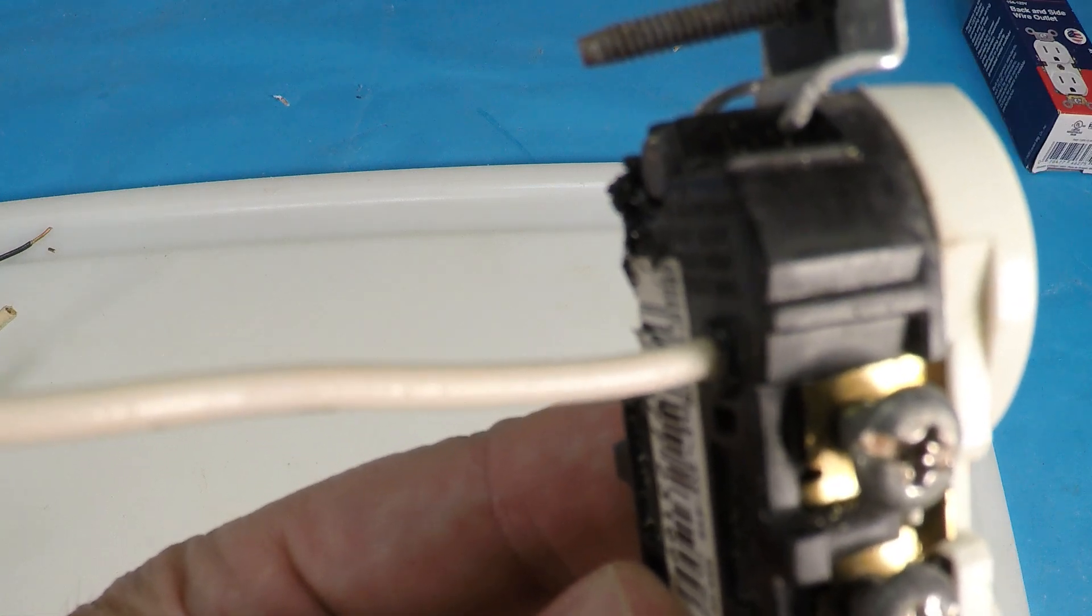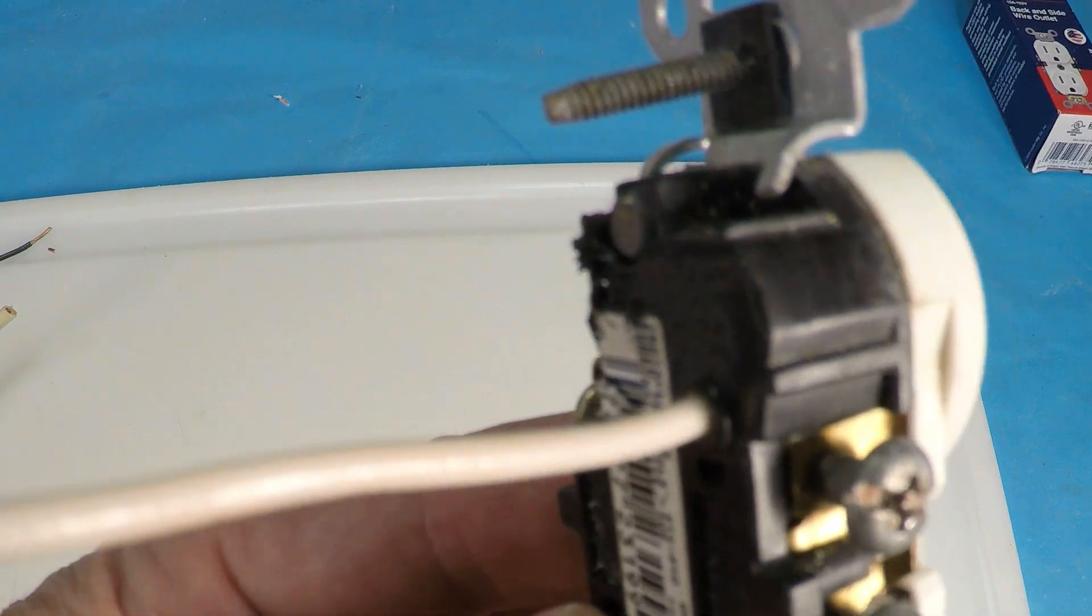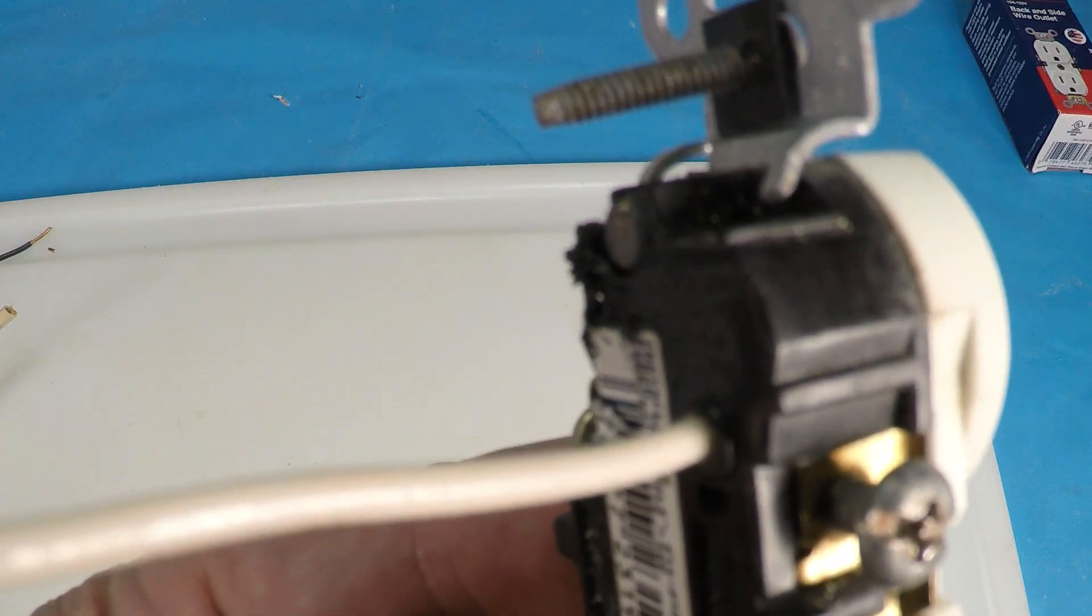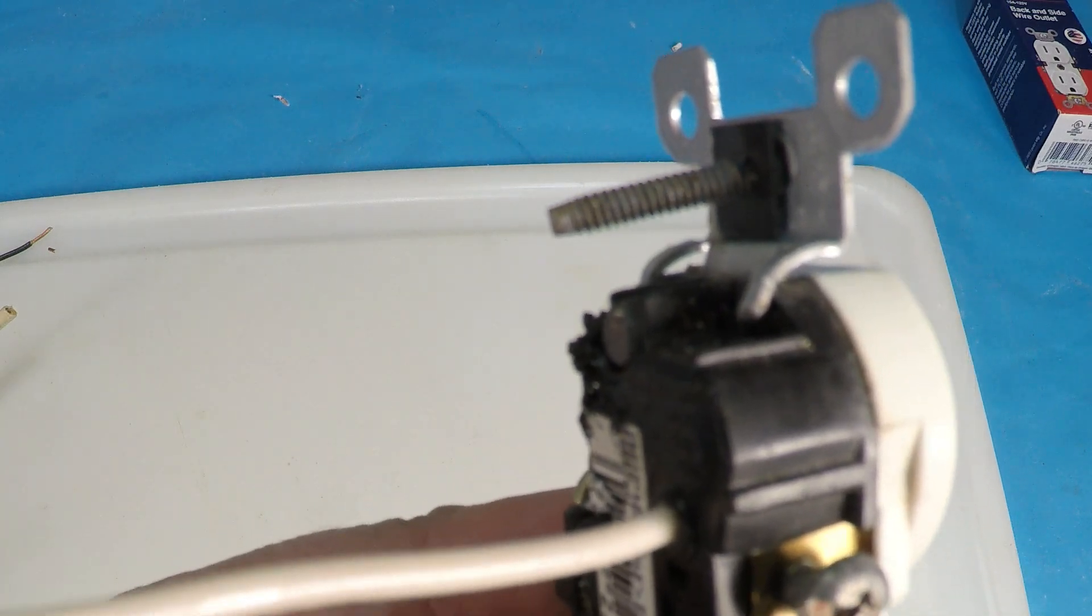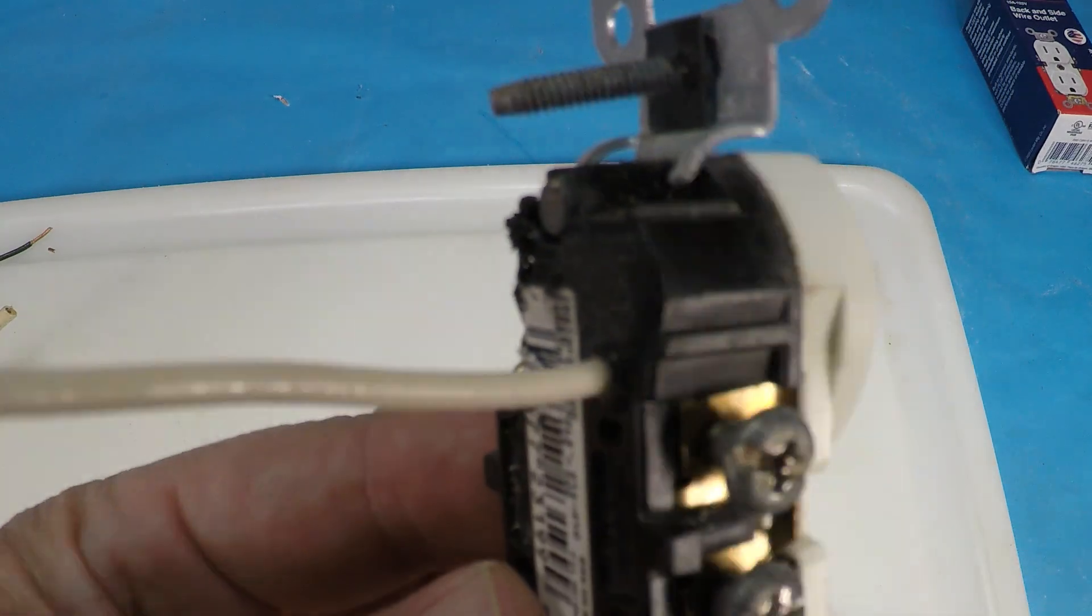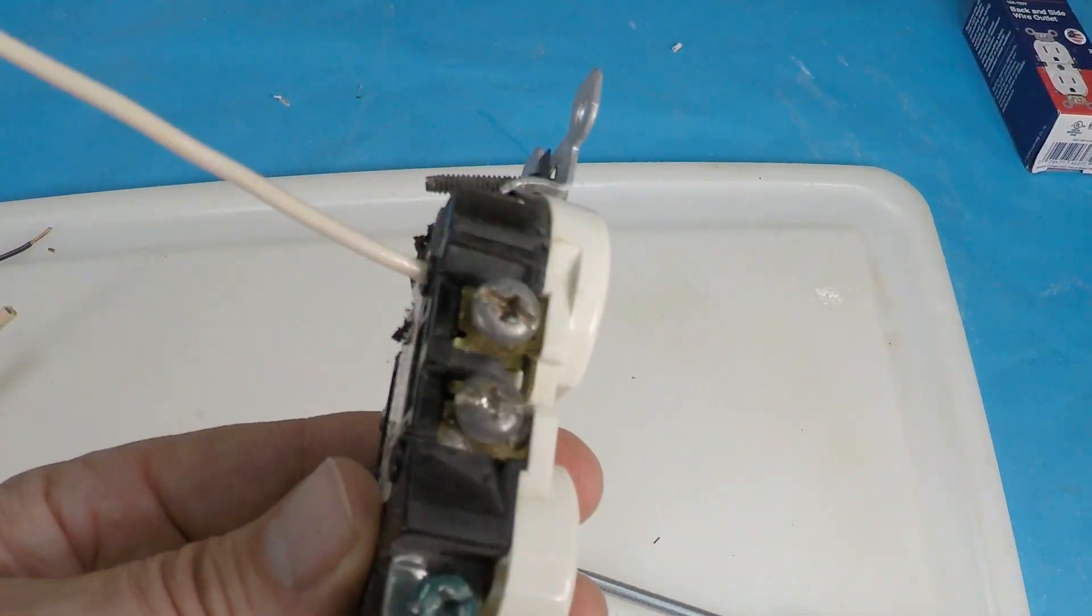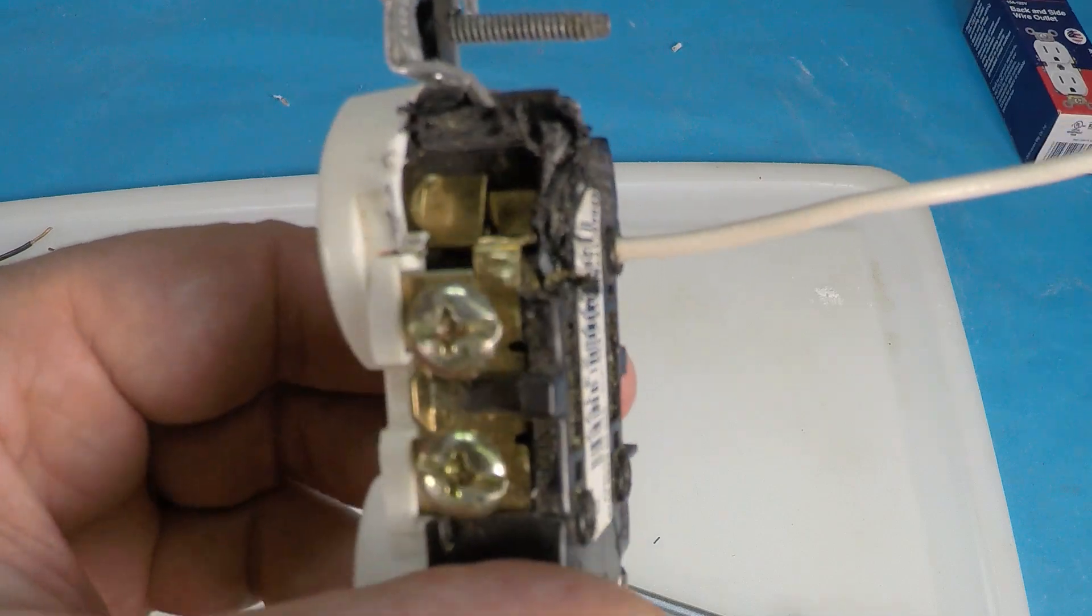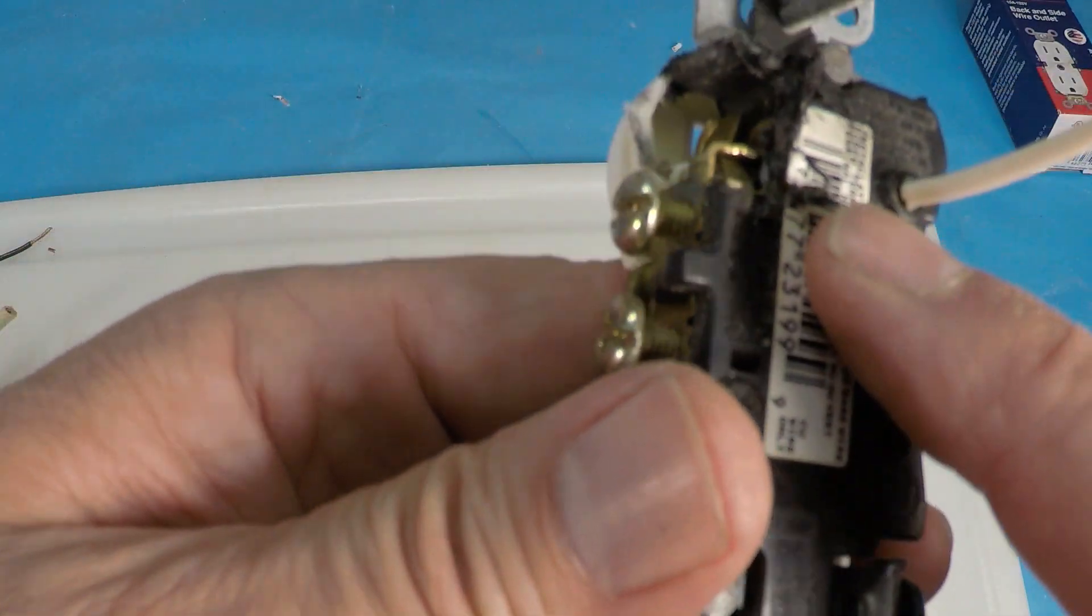Backstabbing should not be anything that you entertain and if you pull out one of your outlets and it's backstabbed, immediately rewire it. The companies are making these outlets for convenience. It's laziness and laziness is going to potentially burn your house down or worse. Now I cut open this outlet on this side so you can see what's going on when you backstab it.